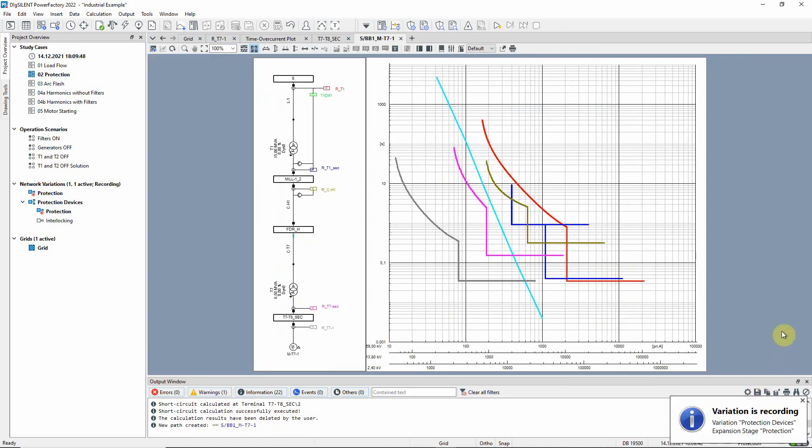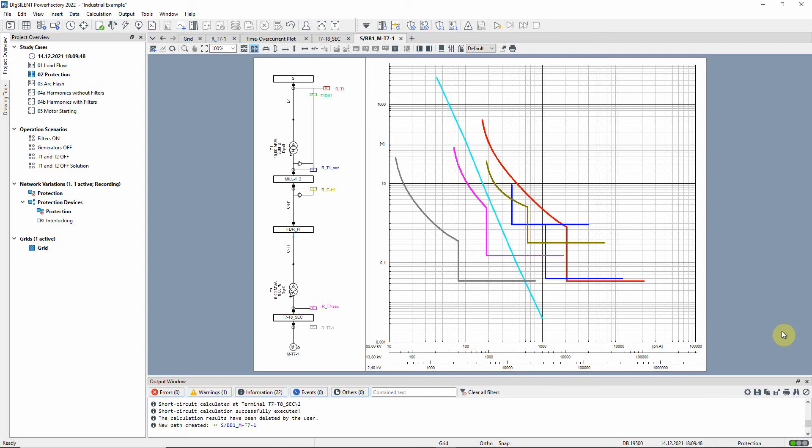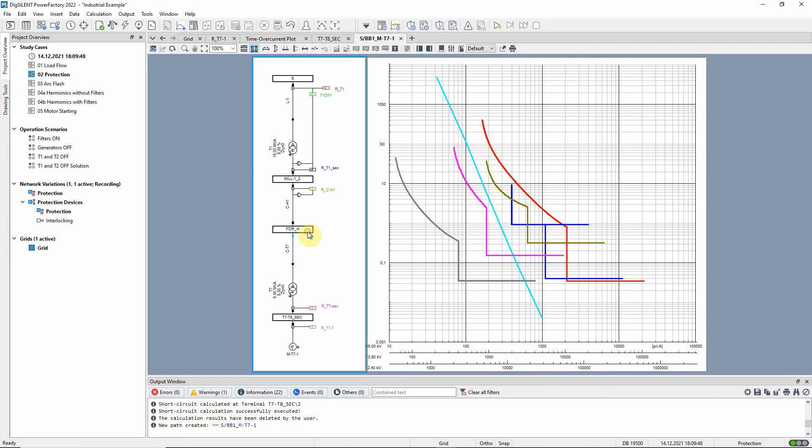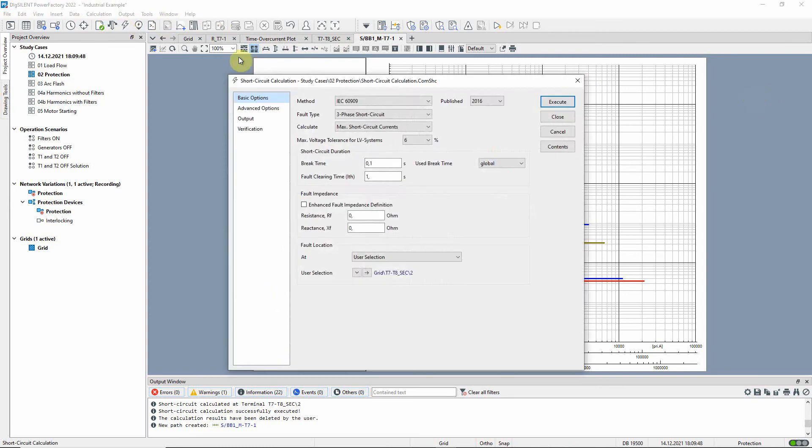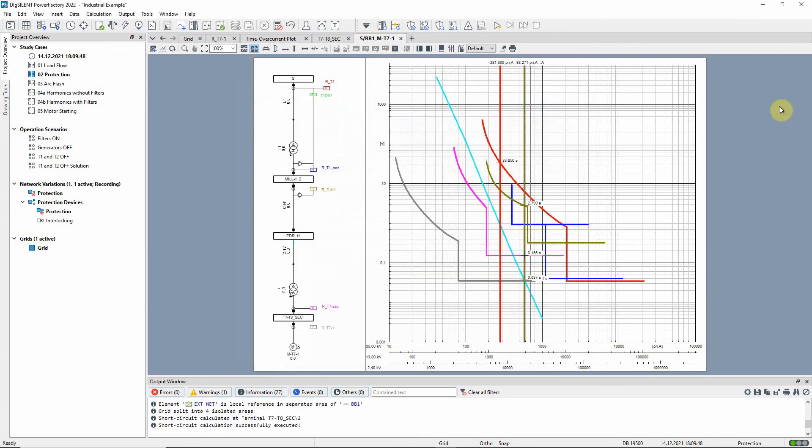The time over current characteristics for all the devices are displayed together with a diagram on the left hand side. The diagram can be edited if required. The short circuit calculation can be run again and the device coordination assessed from the time over current plot.